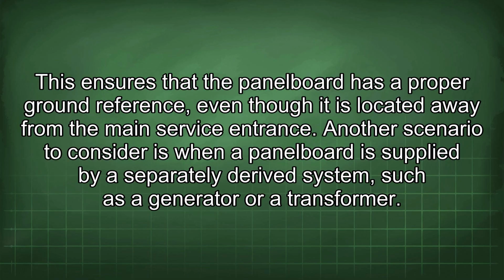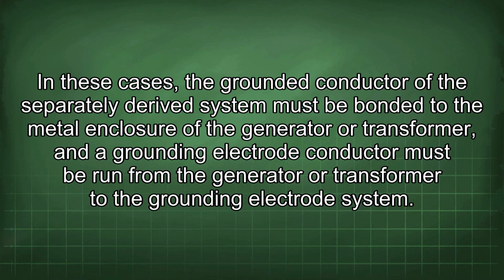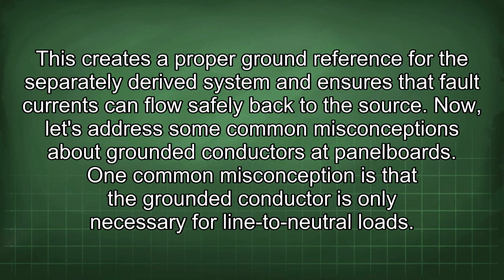Another scenario to consider is when a panel board is supplied by a separately derived system, such as a generator or a transformer. In these cases, the grounded conductor of the separately derived system must be bonded to the metal enclosure of the generator or transformer, and the grounding electrode conductor must be run from the generator or transformer to the grounding electrode system. This creates a proper ground reference for the separately derived system and ensures the fault currents can flow safely back to the source. Now let's address some common misconceptions about grounded conductors at panel boards.